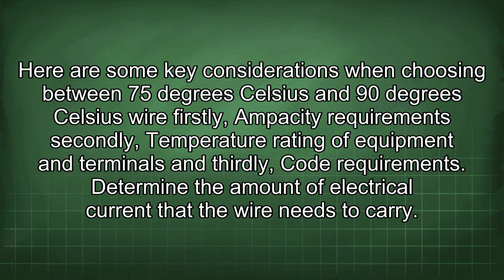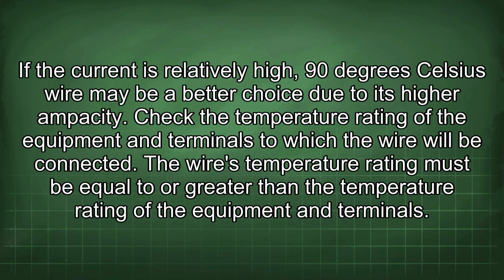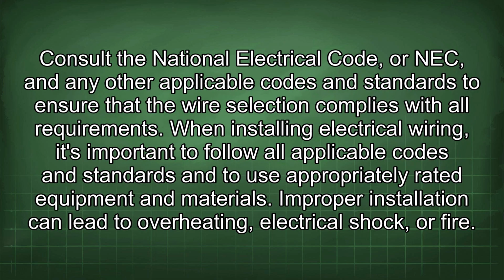And thirdly, code requirements. Determine the amount of electrical current that the wire needs to carry. If the current is relatively high, 90 degrees Celsius wire may be a better choice due to its higher ampacity. Check the temperature rating of the equipment and terminals to which the wire will be connected. The wire's temperature rating must be equal to or greater than the temperature rating of the equipment and terminals. Consult the National Electrical Code, or NEC, and any other applicable codes and standards to ensure that the wire selection complies with all requirements. When installing electrical wiring, it's important to follow all applicable codes and standards and to use appropriately rated equipment and materials. Improper installation can lead to overheating, electrical shock, or fire.